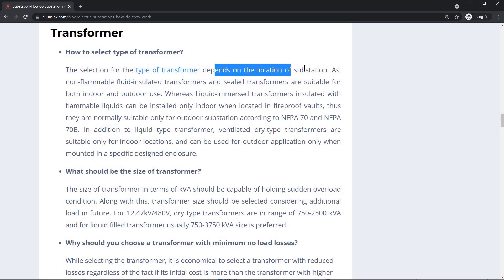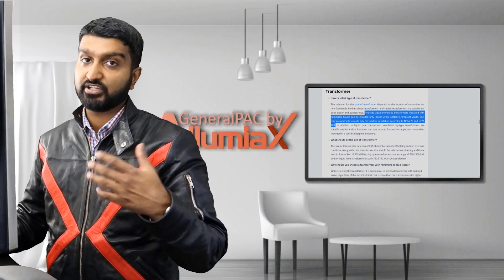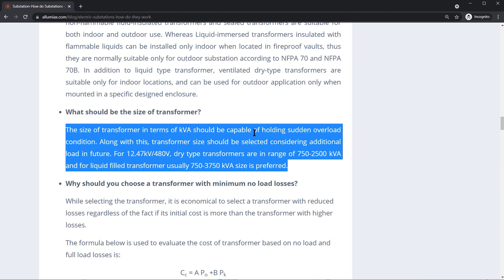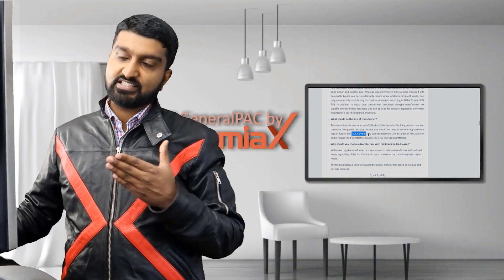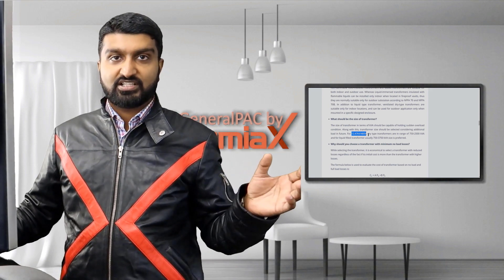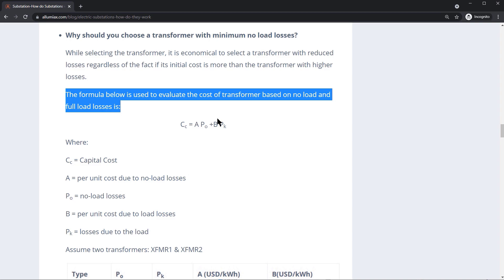The type of transformer depends on the location of the substation. Non-flammable, fluid-insulated transformers and sealed transformers are suited for both indoor and outdoor use. The size of the transformer in terms of kVA should be capable of handling sudden overloads. 12.47 kV to 480-volt dry-type transformers are in the range of 750 to 2500 kVA. These are very common for utility transformers serving 480-volt customers.